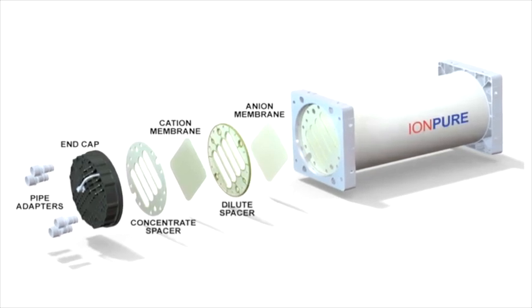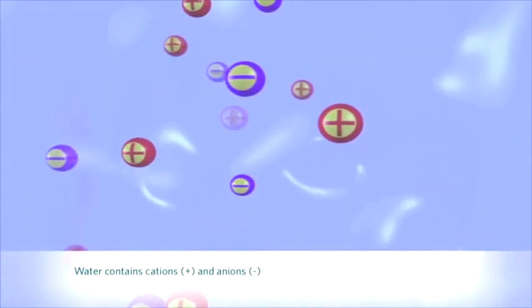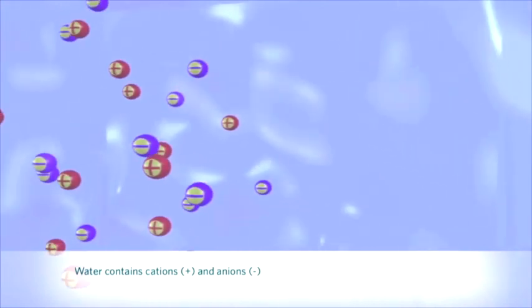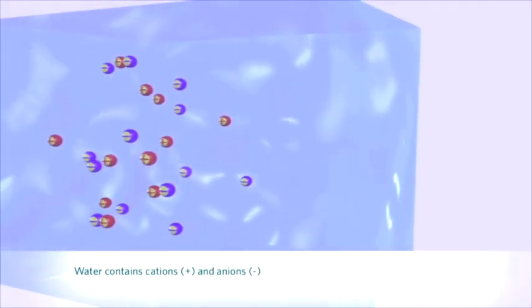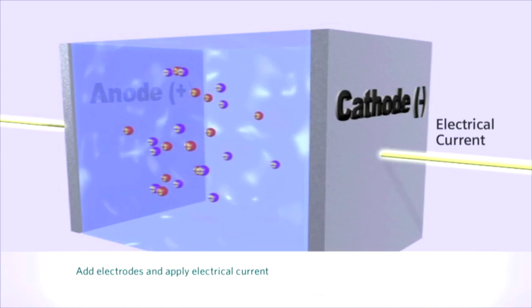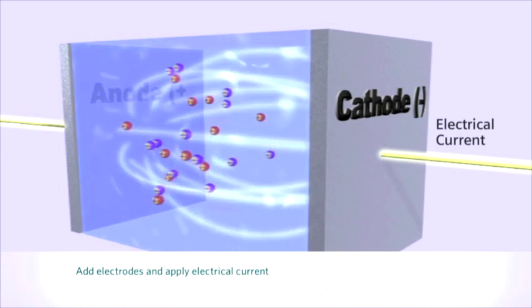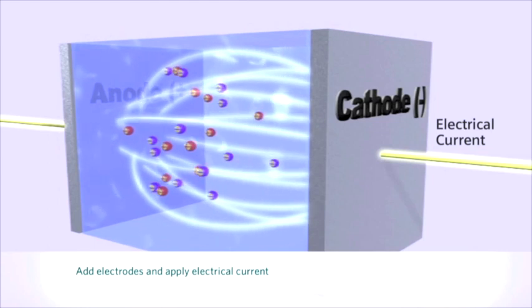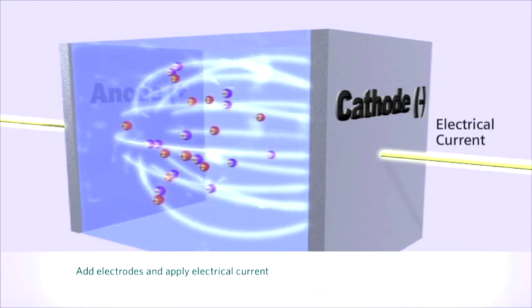To understand how the patented IonPure CEDI technology actually works, let's go down to the molecular level and take a look at some water containing ions. Water contains positively charged cations, represented by plus signs, and negatively charged anions, represented by minus signs. When a pair of electrodes is inserted and an electrical current applied, the electric field drives the cations in the direction of the cathode and at the same time drives the anions in the opposite direction toward the anode.